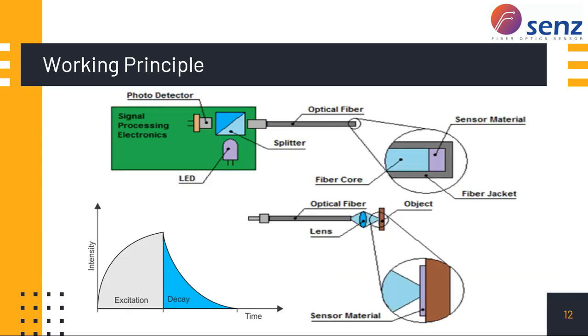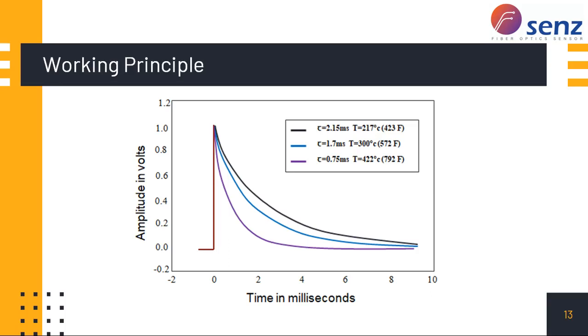So this is the diagram. We have a photo detector, the LED light, and our fiber optic cable. At the end of the fiber optic cable, we have a fluorescence material. The LED light goes to the fluorescence material, it will reflect back, and this will be sensed by the detector. The detector would sense the decay rate, and we will find out what the rate is here at the photo detector. It would change with temperature. As the temperature increases, the decay rate will become shorter.